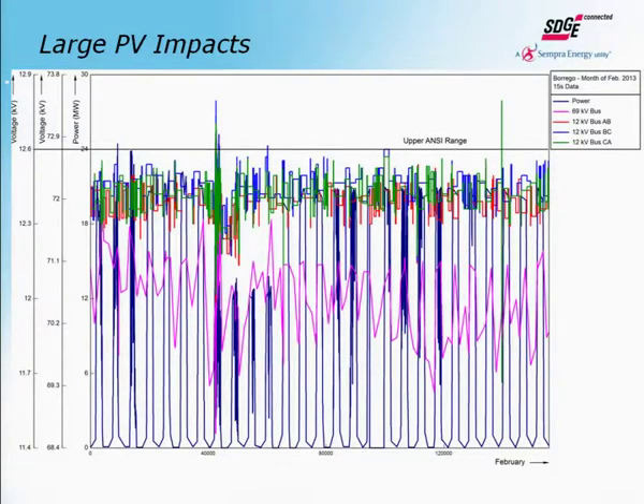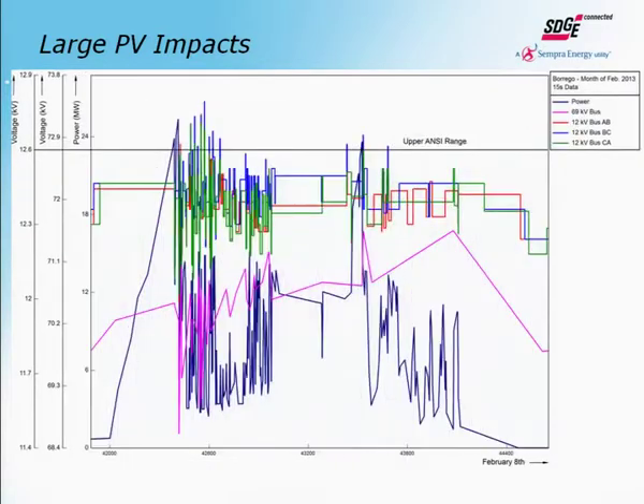So here's a large PV system, in the desert in East County. This shows every single day of February. If we zoom in here, the blue is the actual power production, the pink is the 69 kV bus voltages, and up here are the 12 kV distribution bus voltages.